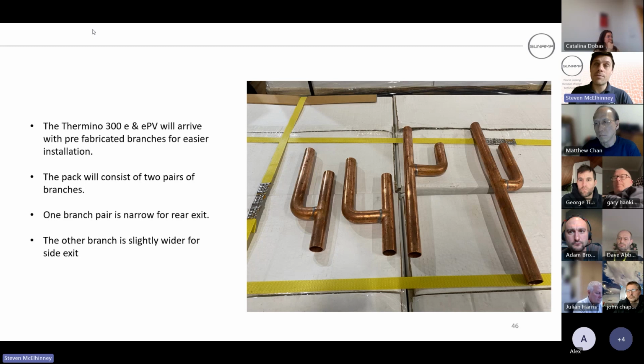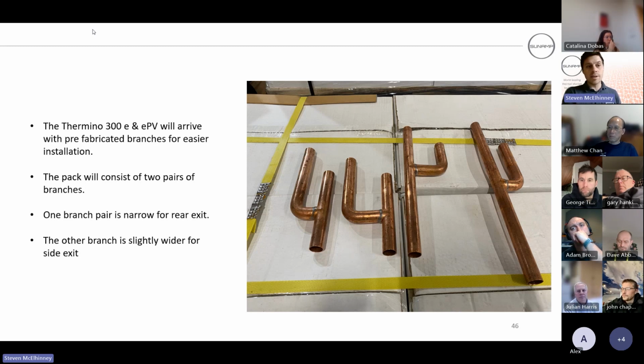To be honest, I've seen it before with a Thermino 70. Someone's done that, and they've had two different outlets. The old Thermino 70s used to be dual ported, and we've stopped doing that now. But what they did was put one port feeding the shower room, so sink and shower, and then the other port feeding the sink in the kitchen. And what they were getting is, if somebody was running the shower at the same time and running a basin of water, it was just killing the capacity of that.